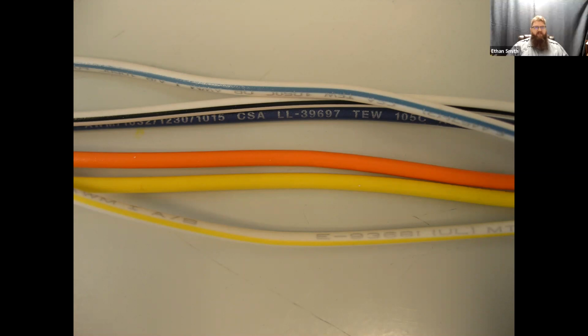Yeah, there's a lot of information that you can pull off a wire. This becomes important if you're going to replace something. You'll notice that this one has the insulation type here as a TEW. It has a thermal rating on that insulation, which is 105 C. Okay, you can usually Google this stuff and come up with answers. Or if you've invested in one of those little Ugly's reference books that I talked about last week, it has a whole section in here about interpreting wiring nomenclature. So it comes in handy for that if you're going to have to replace something. So make sure you're paying attention to your wire.